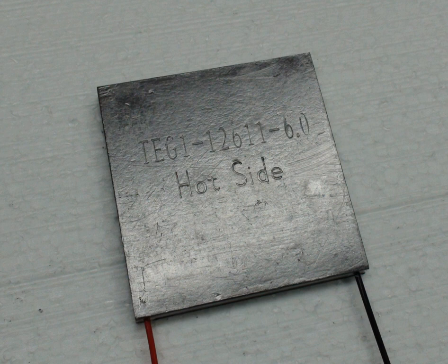The Peltier coefficient depends on temperature and the materials the TEC is made of. In refrigeration applications, thermoelectric junctions have about one-quarter the efficiency compared to conventional means. They offer around 10-15% efficiency of the ideal Carnot cycle refrigerator, compared with 40-60% achieved by conventional compression cycle systems, reverse Rankine systems using compression and expansion. Due to this lower efficiency, thermoelectric cooling is generally only used in environments where the solid-state nature, no moving parts, low maintenance, compact size, and orientation insensitivity outweighs pure efficiency.